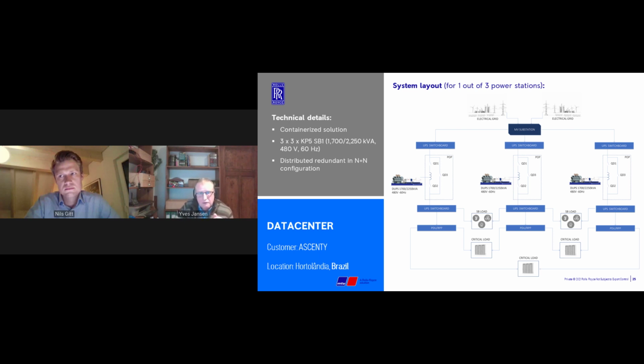At Ascenty, this is a data center - the critical loads are the IT racks, the IT loads, and the essential loads are the mechanical loads like the chillers. At Ascenty, the topology is distributed redundant in the N plus N configuration, a tier 4 configuration.